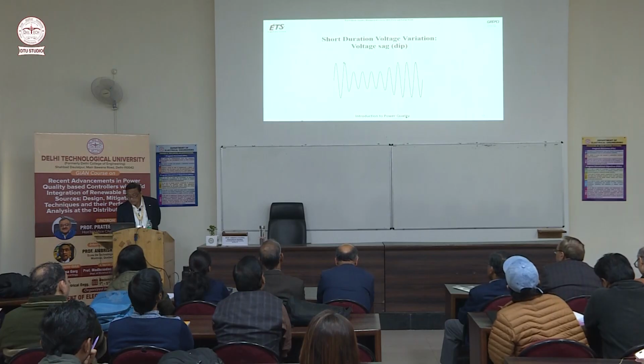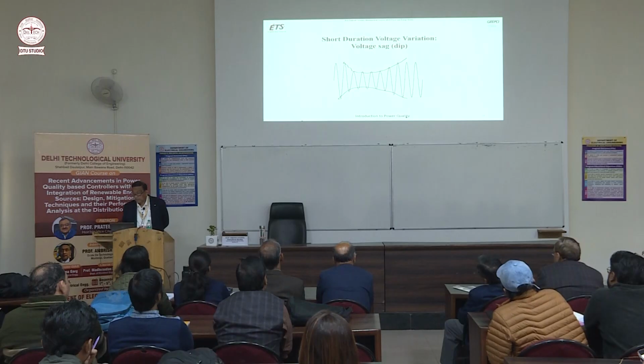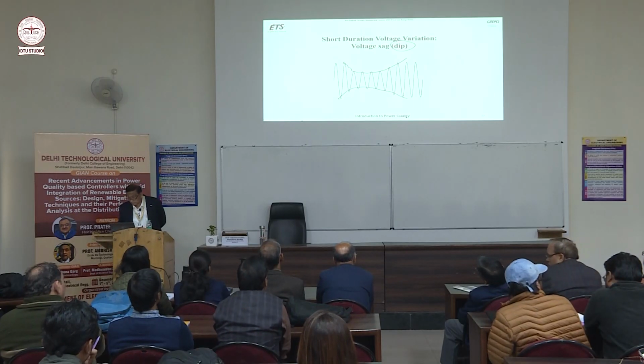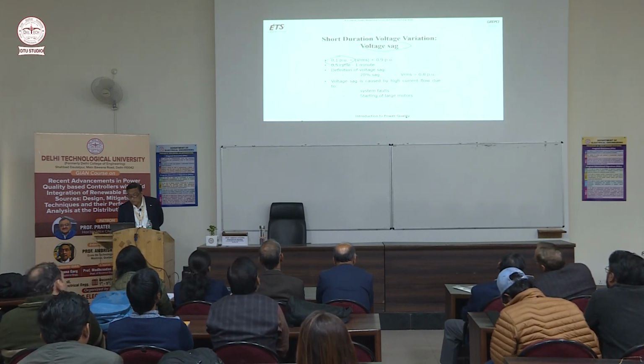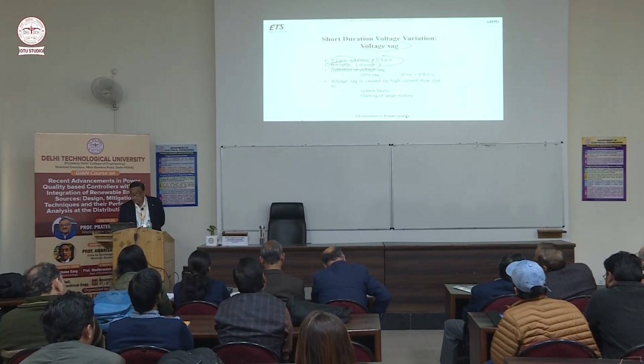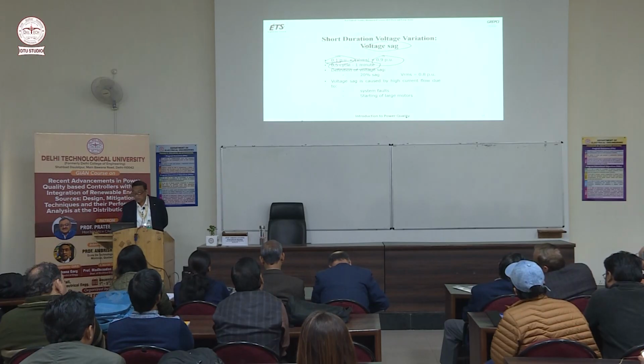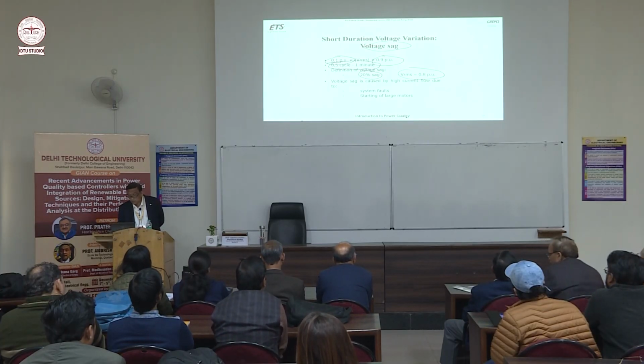Short duration voltage variation. Okay, so you can see for short duration, for a few cycles, you have voltage sag. In Europe, they call it dip. So voltage sag may be between 0.1 pu to 0.9 pu, between half cycle and 1 minute. So that is short duration voltage sag. So if we say 20% sag, it means VRMS is 0.8 pu. Voltage sag is caused by high current flow due to system faults, starting of large motors, as we have already discussed.